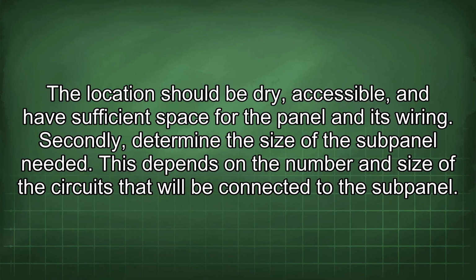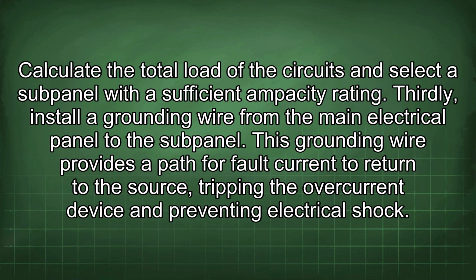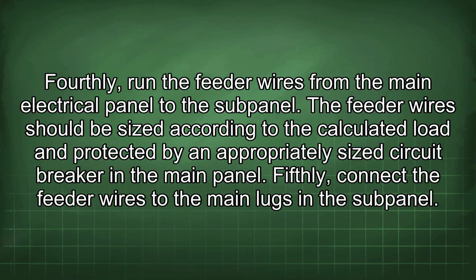Secondly, determine the size of the subpanel needed. This depends on the number and size of the circuits that will be connected to the subpanel. Calculate the total load of the circuits and select a subpanel with a sufficient ampacity rating. Thirdly, install a grounding wire from the main electrical panel to the subpanel. This grounding wire provides a path for fault current to return to the source, tripping the overcurrent device and preventing electrical shock. Fourthly, run the feeder wires from the main electrical panel to the subpanel.